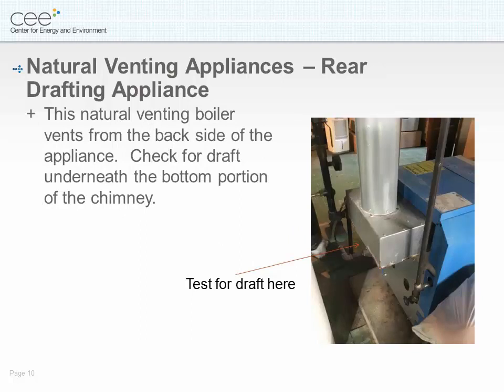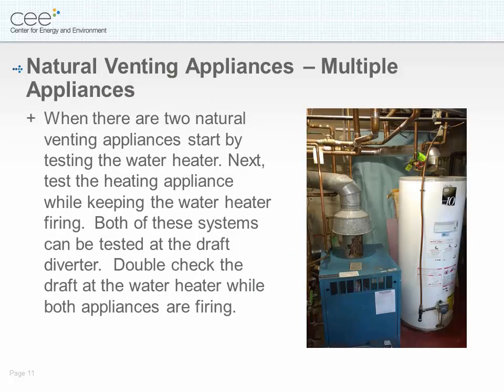Natural venting appliances — rear drafting appliance. This natural venting boiler vents from the back side of the appliance; check for draft underneath the bottom portion of the chimney. When there are two naturally venting appliances, start by testing the water heater. Next, test the heating appliance while keeping the water heater firing. Both of these systems can be tested at the draft diverter. Double check the draft at the water heater while both appliances are firing.